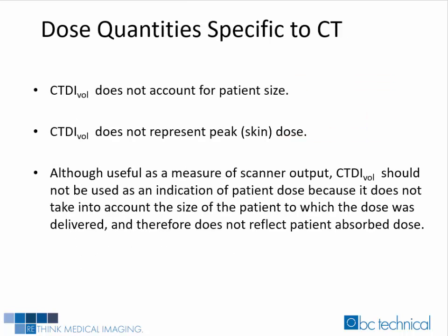Please remember that CTDI volume does not account for patient size, and it does not represent peak dose. Although useful as a measure of scanner output, CTDI volume should not be used as an indication of patient dose, because it does not take into account the size of the patient to which the dose was delivered, and therefore does not reflect patient absorbed dose.